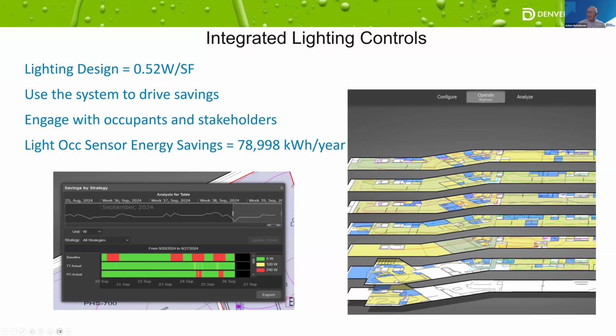If you're looking at doing this or have already done it, you really need to engage with the occupants. When we moved in, we only had 3 or 4 months before COVID, and everybody came back in 2022 basically. A lot of people didn't understand that the occupancy sensors for lighting controls also controlled the HVAC. Some weren't sitting in the dark, but their sensors weren't working because they were blocked by piping or diffusers, and they didn't realize they could call in and say things like they shouldn't need to turn lights on every 15 minutes, or that it felt a bit cooler than it should.